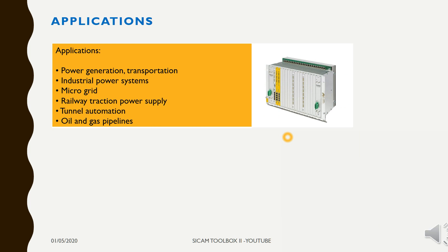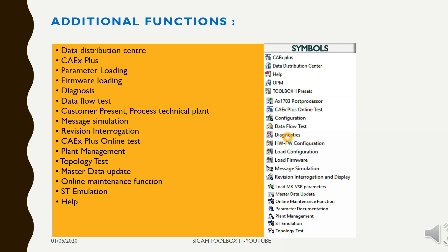Here we will talk about primary functions of Toolbox 2. OPM2 is the central engineering software. It is used for data modeling where you can create signals within process technique. After creating signals you can transform them into system technique — they will be assigned automatically within peripheral modules defined within the automation unit. There are some additional functions within the software. The data distribution center is used to import or export the backup with the engineering station.